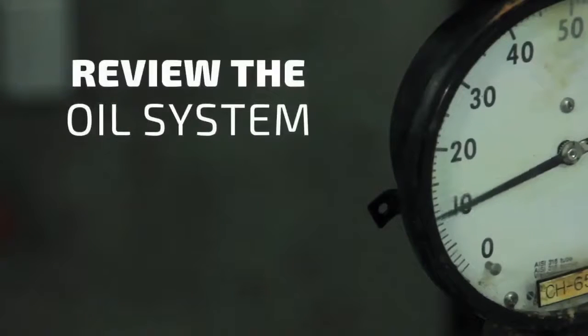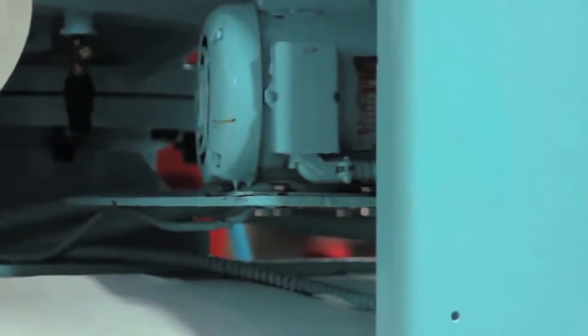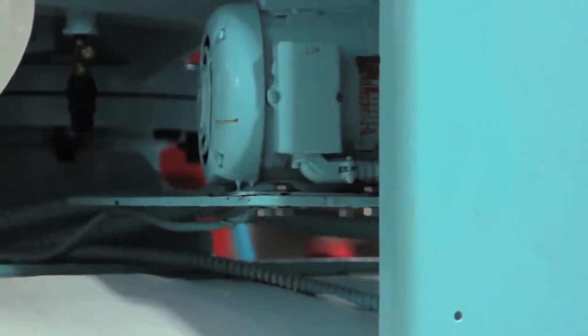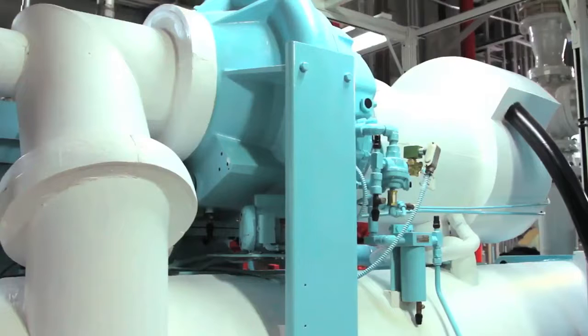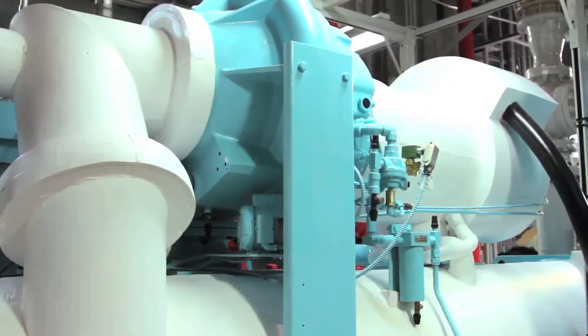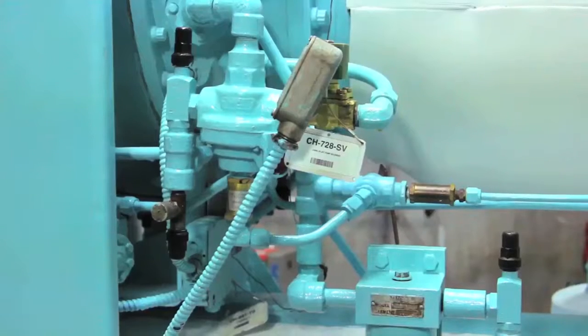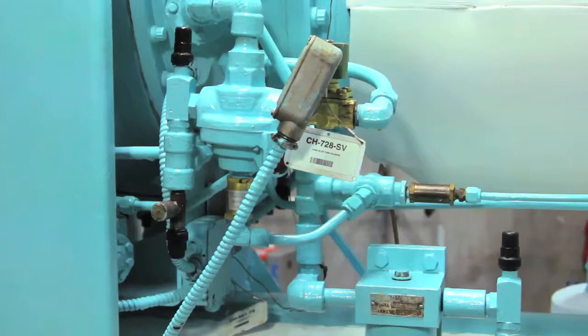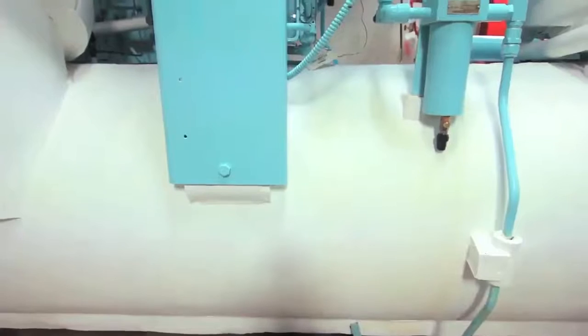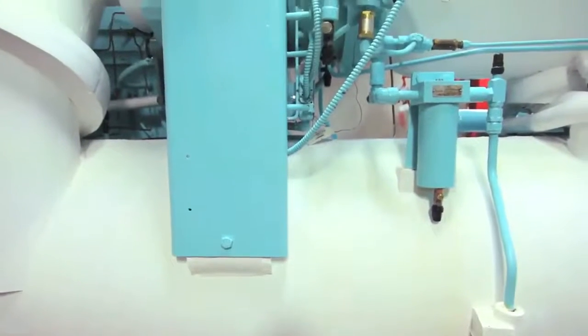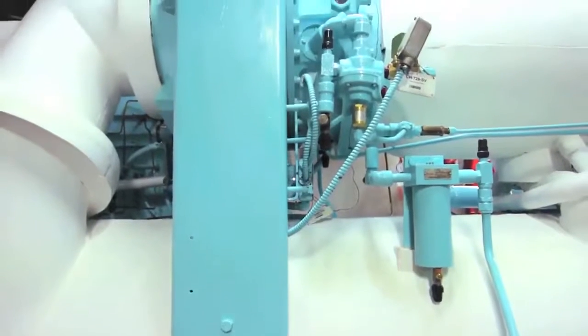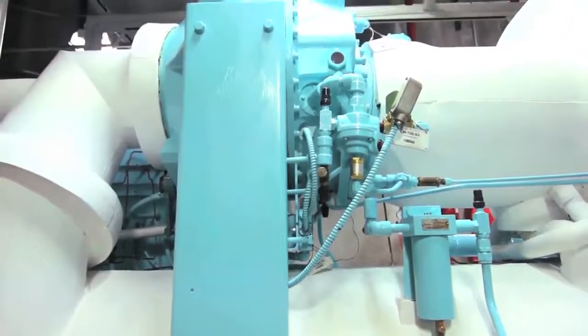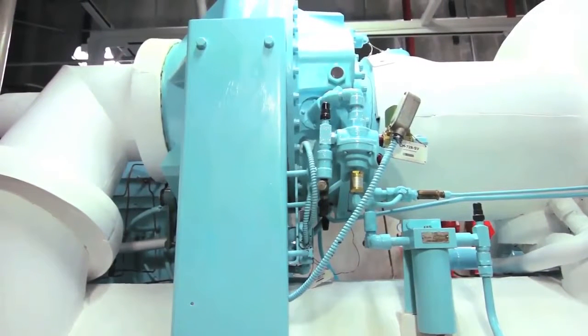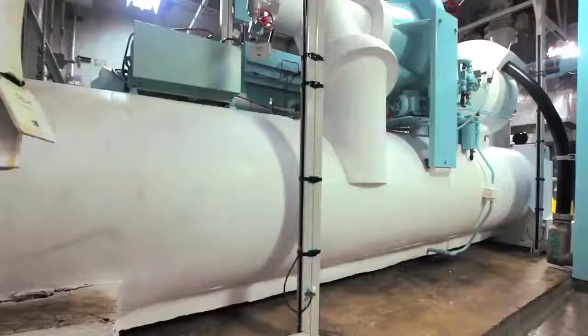Let's review the oil system. The oil circulation system of this machine has 4 oil pumps. The auxiliary oil pump is a motor-driven positive displacement pump. The second pump is called the jet pump. The pump operates by oil passing through it, spinning up a small ring, boosting the output pressure. These 2 pumps are used on startup. The auxiliary oil pump and jet pump pre-lube the machine.